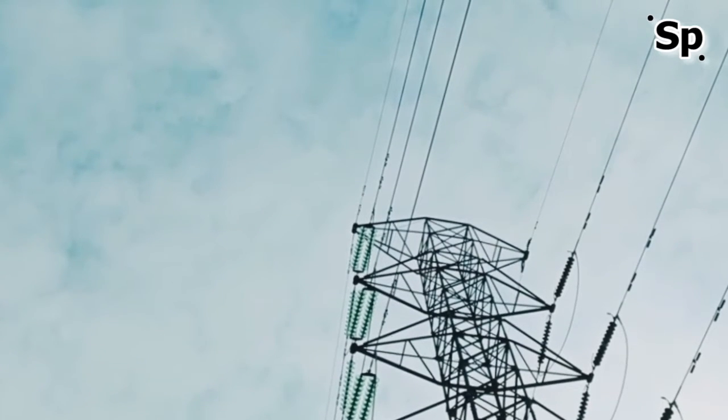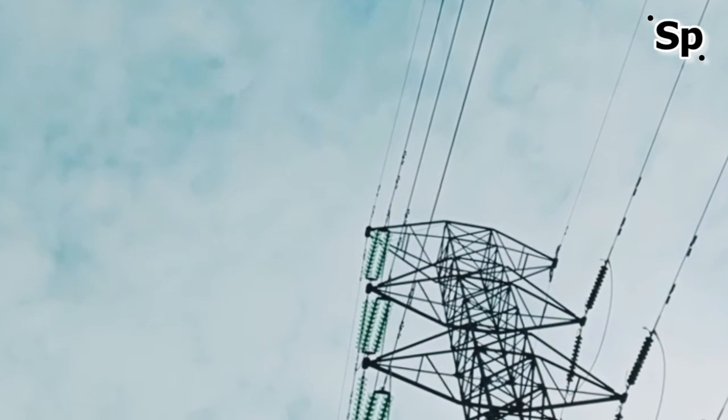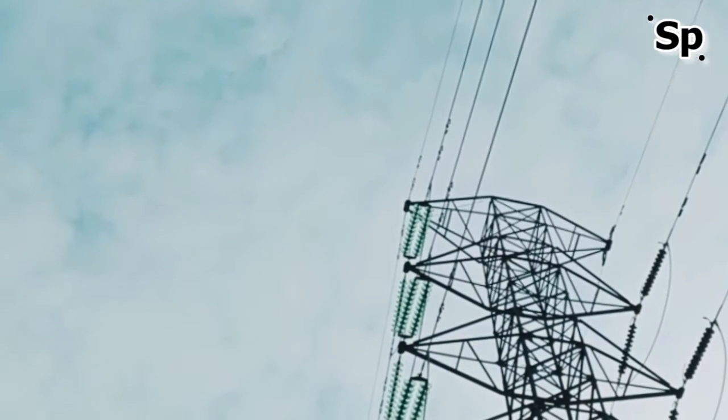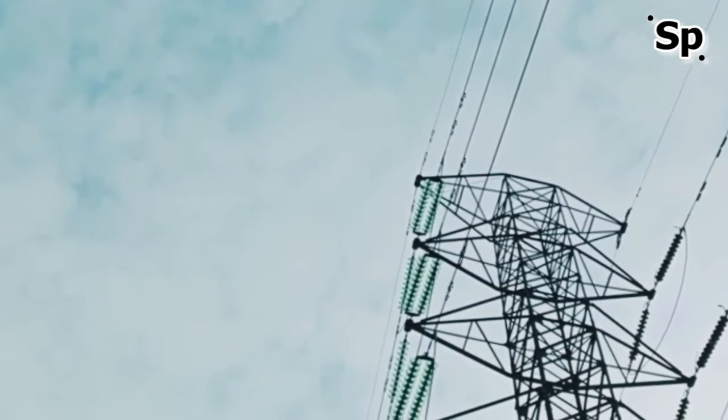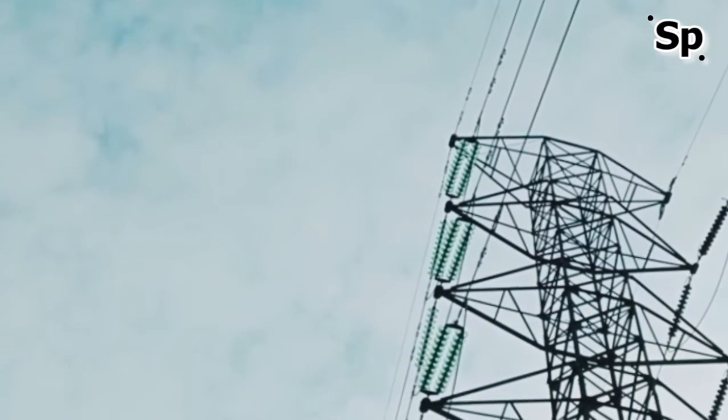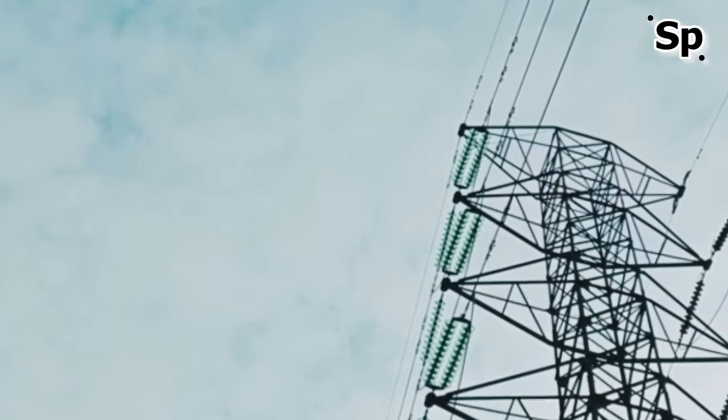The center part of the conductor carries little current, but contributes weight and cost to the conductor. Because of this current limitation, multiple parallel cables, called bundle conductors, are used when higher capacity is needed. Bundle conductors are also used at high voltages to reduce energy loss caused by corona discharge.